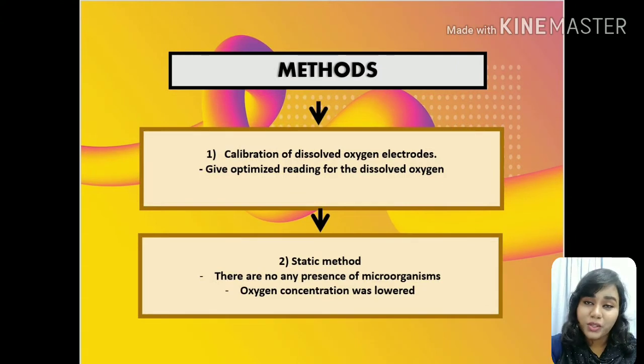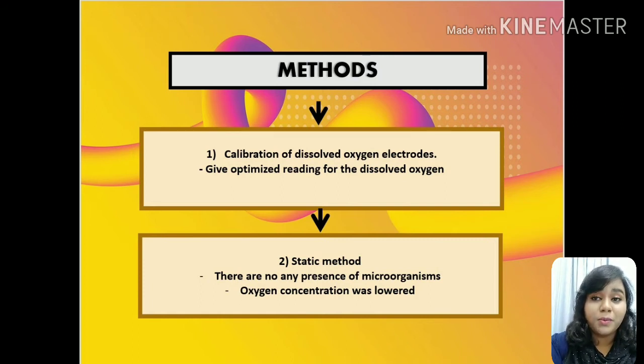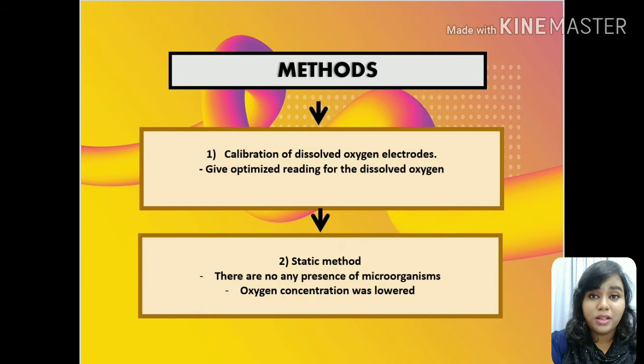As for the methods, there are two steps to be followed. Firstly would be the calibration of the dissolved oxygen electrode. This is done because after the sterilization, it will give the optimized reading for the dissolved oxygen, and the calibration is then performed under process control. The second step is the static gassing-out method, during which the oxygen concentration of the solution is lowered by static gassing-out with nitrogen gas.